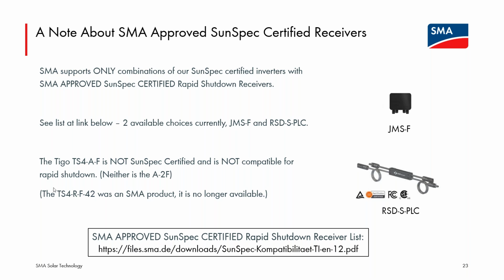We started with the SMA TS4-R-F-42. That was an SMA product. It is no longer available. That was the third device on this list. So the two commercially available devices on that SMA approved list are the JMS-F and the RSD-S-PLC.